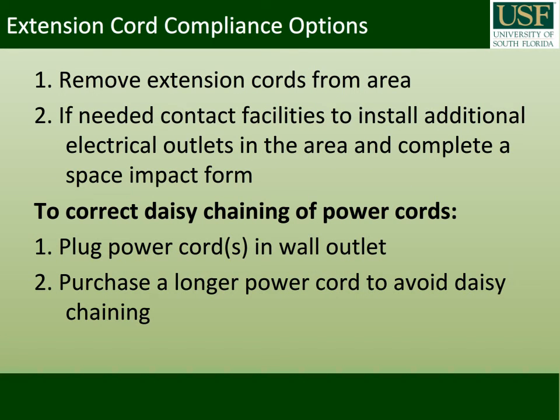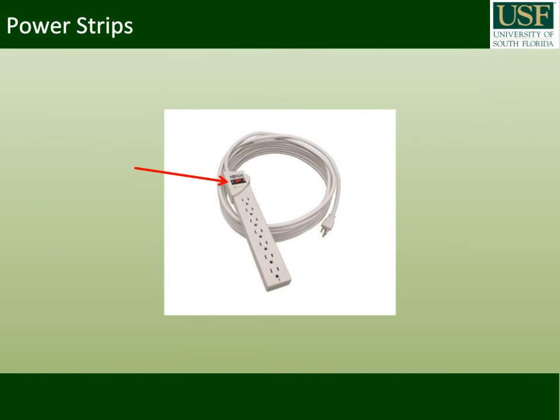To stay compliant, one must remove any seen extension cords from the area. Another option is to contact facilities to have additional electrical outlets added in the area by completing a space impact form. Before doing this, see if there are any other extra outlets needed in the building and put them all on the same form. Power strips come in lengths up to 25 feet, and as the red arrow points out, it must have a circuit breaker to be considered a power strip.